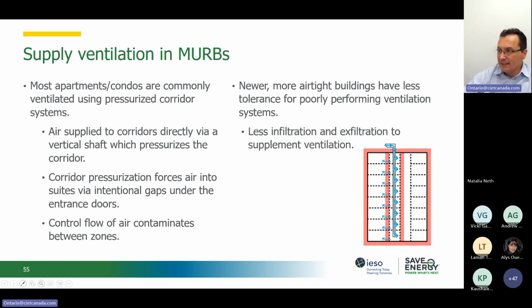But in the way we design it, as presented in the diagram on this slide here, we supply air in the corridors, and that air will be exhausted through units. Units have a slight opening under the doors to allow this airflow to penetrate from the corridors. Now, as we move towards more efficient buildings, newer, tighter buildings would require some form of ventilation dedicated to each unit. So we can't really rely on this system that was pushing air in the corridors to pressurize and then push air under the door to compensate for the air that was eliminated by the exhaust fans in the units.